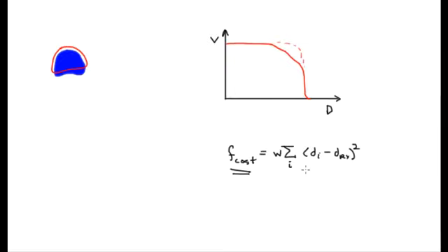So, for example, if it's a PTV, maybe the W factor is very high because you want it to be very uniform in all the pixels. There are other organs at play here. So let's draw in the rectum behind this, and that will have a dose distribution within it, and it will have a DVH as well. So maybe the DVH looks like this. And then we're going to set a point here for this OAR. There'll be one for the PTV too, but I'm not going to draw that.